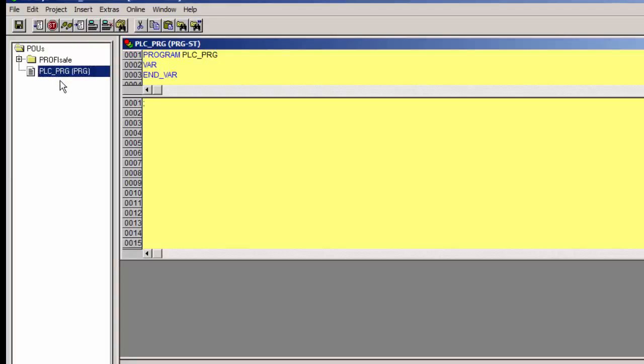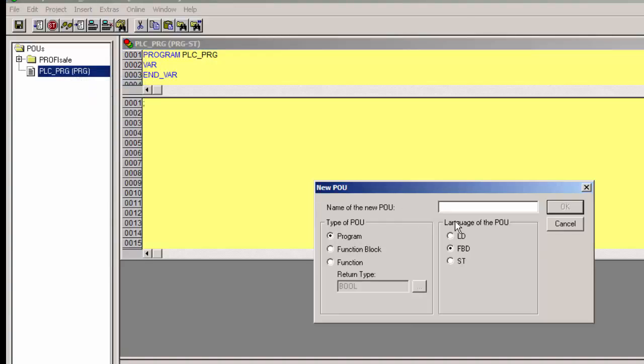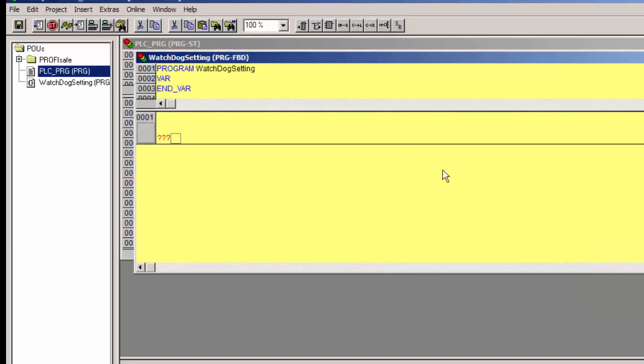So we create one new POU called watchdog setting, and program the watchdog setting function block, with a time value of 100 ms. This being a separate POU, this needs to be called in the main POU, that is PLCPRG.